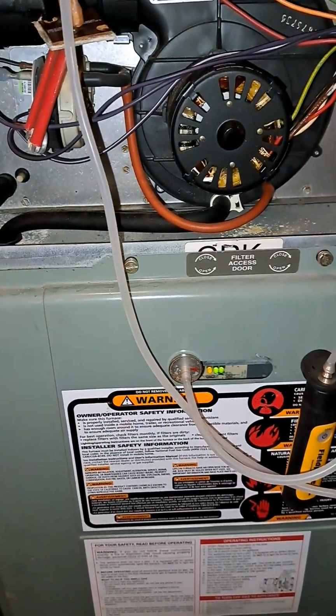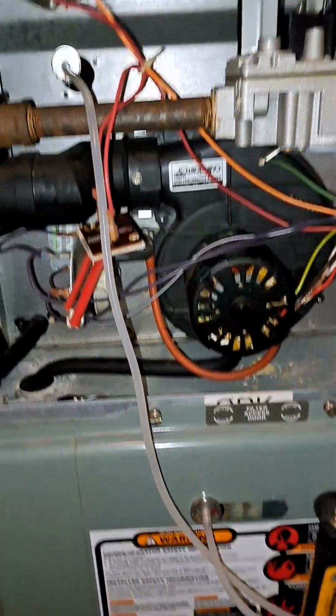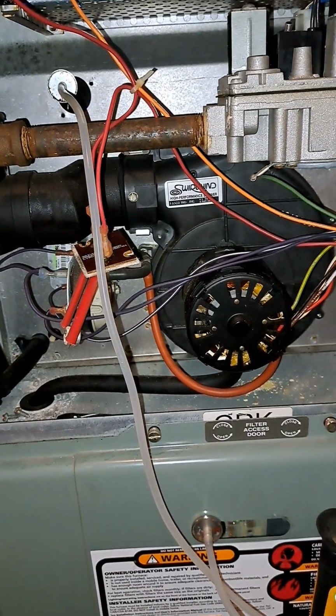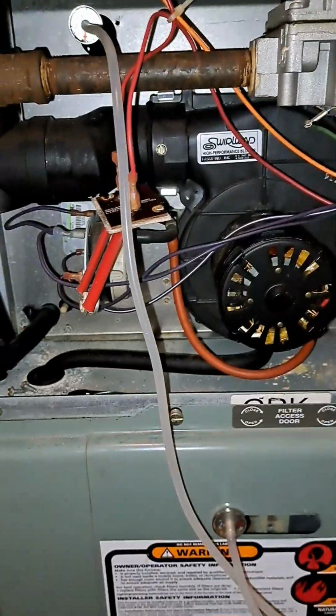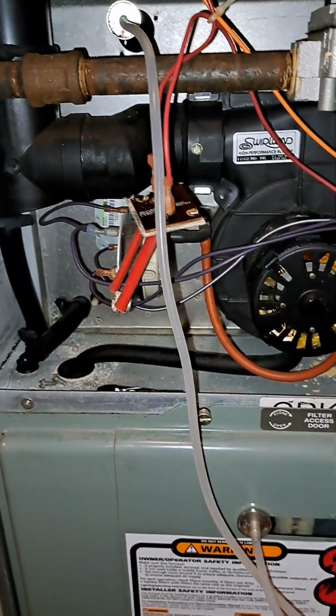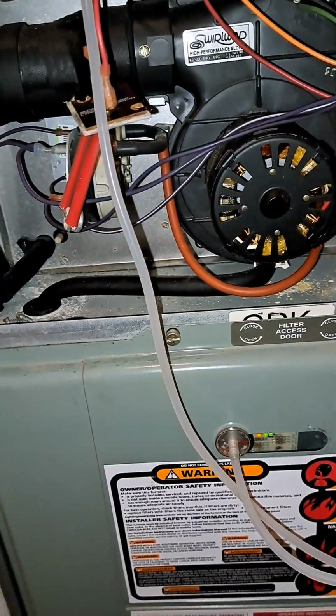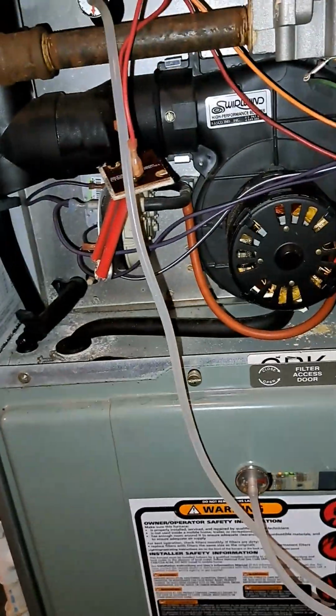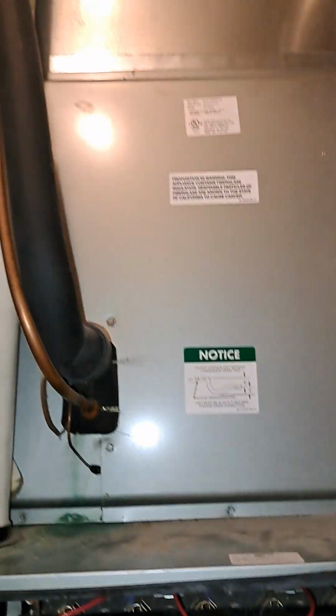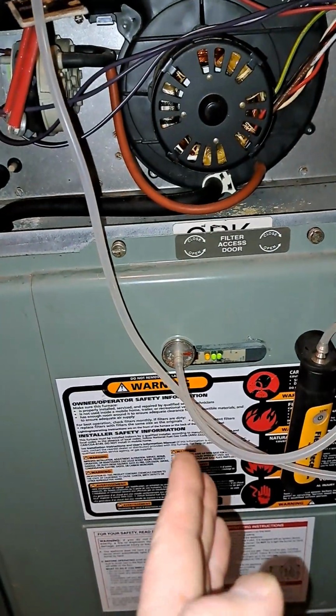Once you get it going, you'll know your static pressure, and that gives you an idea, especially if you're having this trip a bunch. Where's it coming from? Whichever number's higher, right? If it's higher on your supply, your restriction's from there on. If your number's higher on the negative, your return, it's from there on.